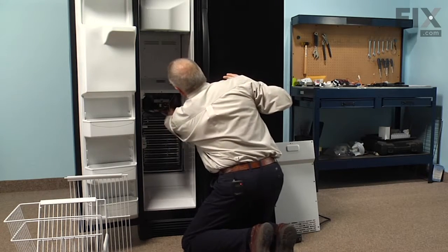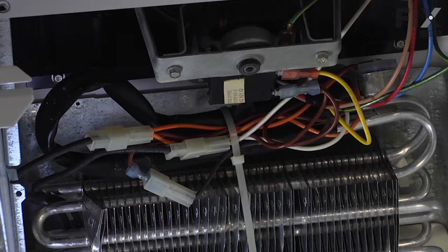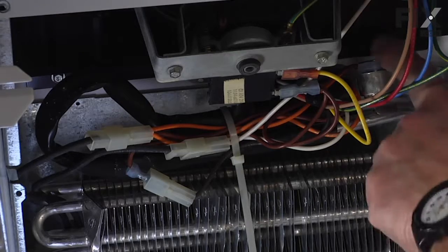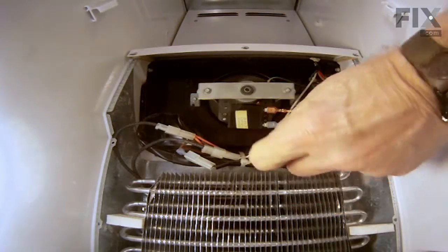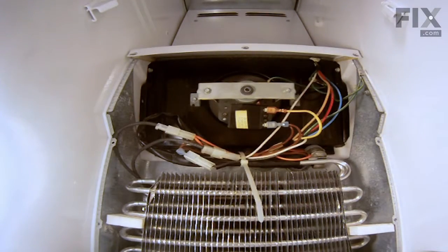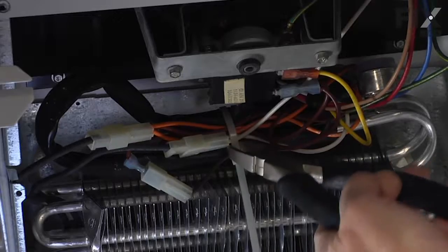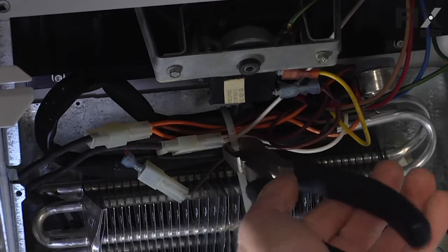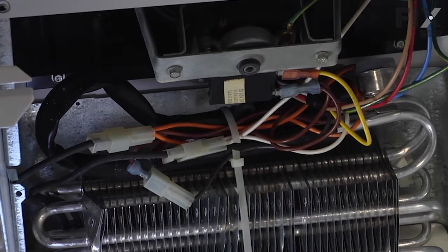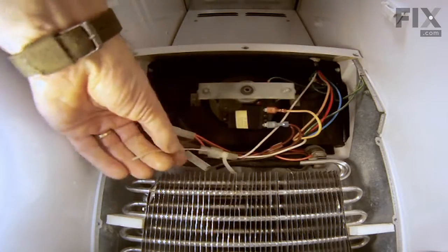Now with the evaporator cover removed, we have access to the bi-metal thermostat. It's located in the upper right corner here and the associated wiring harness. The first thing we'll do is cut that wire tie and remove it. Take care that we don't damage the refrigeration tubing or any of the wires, and pull that out of the way.